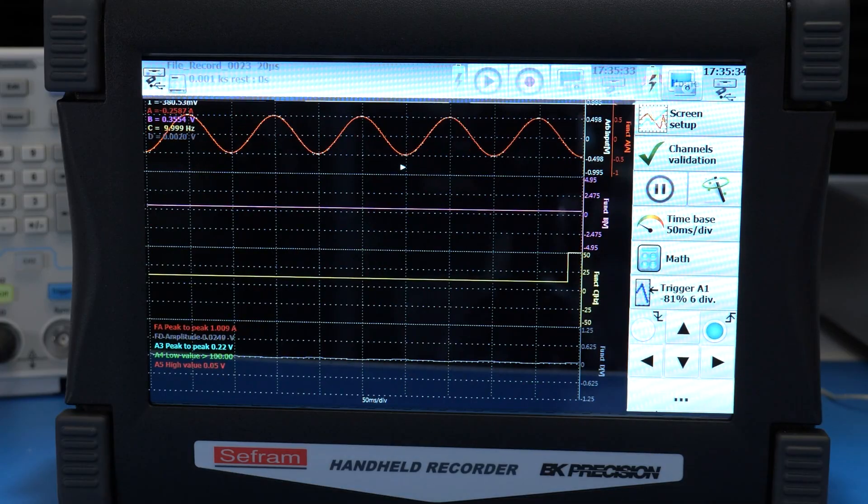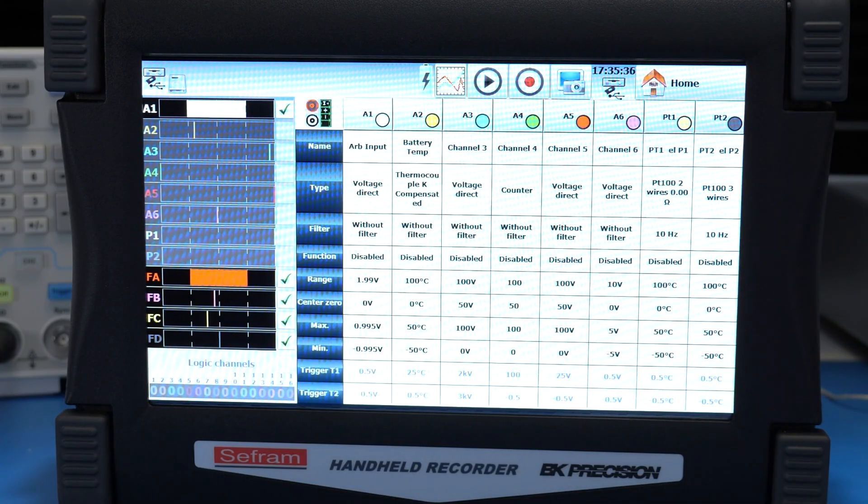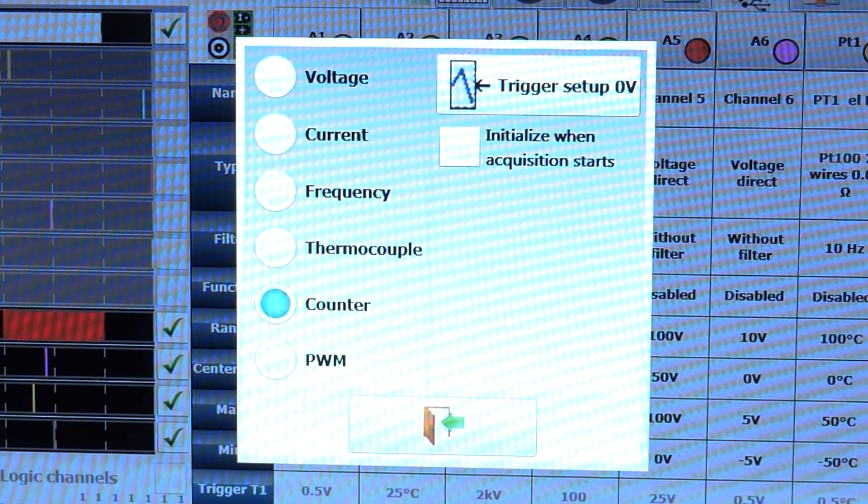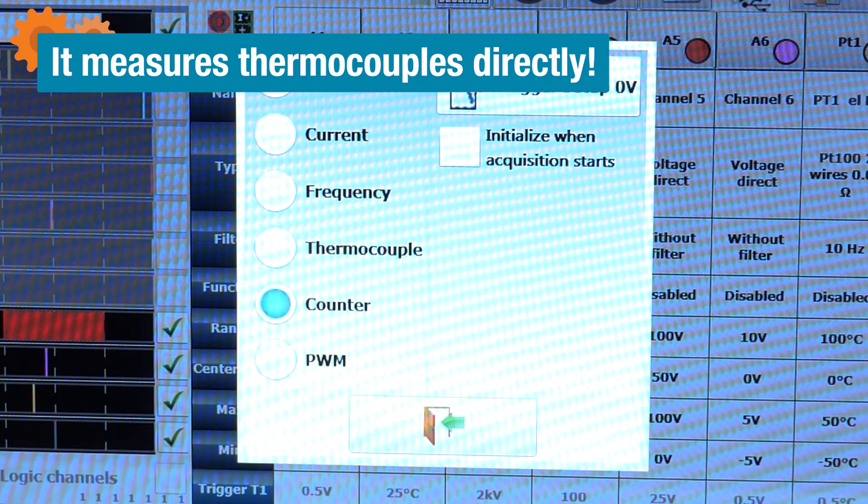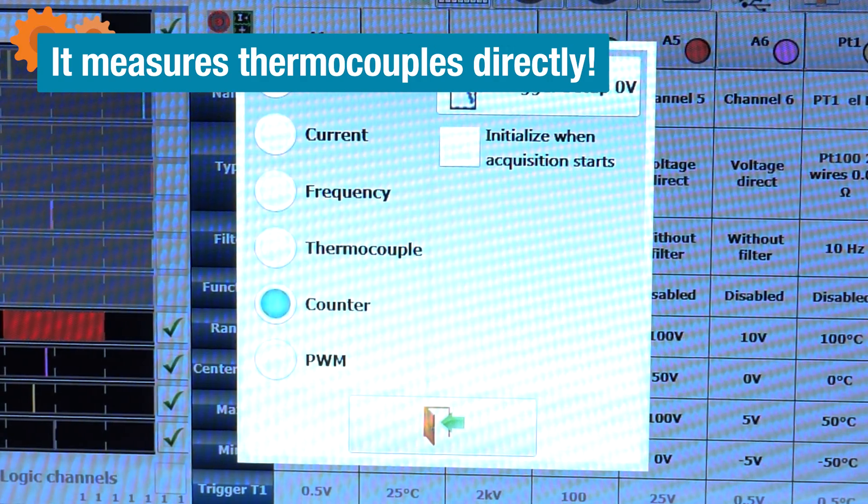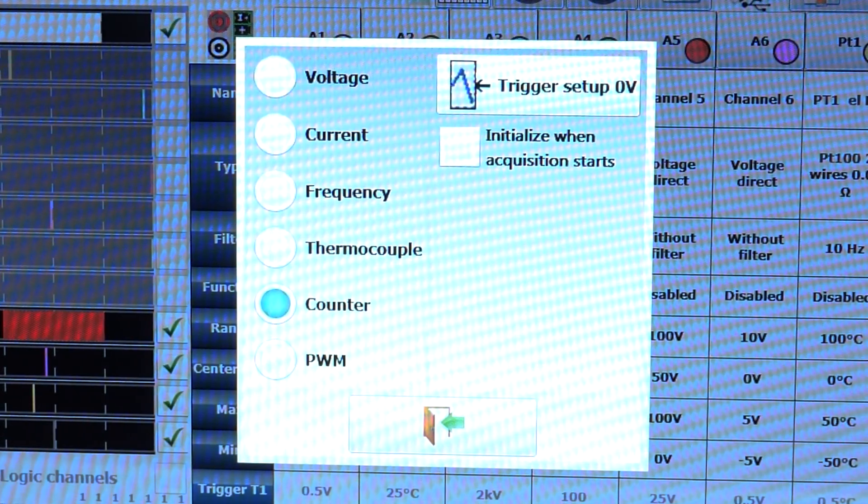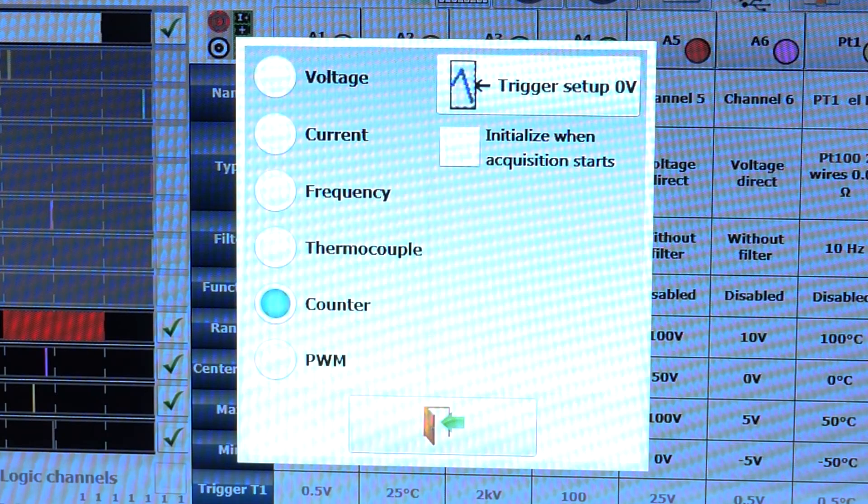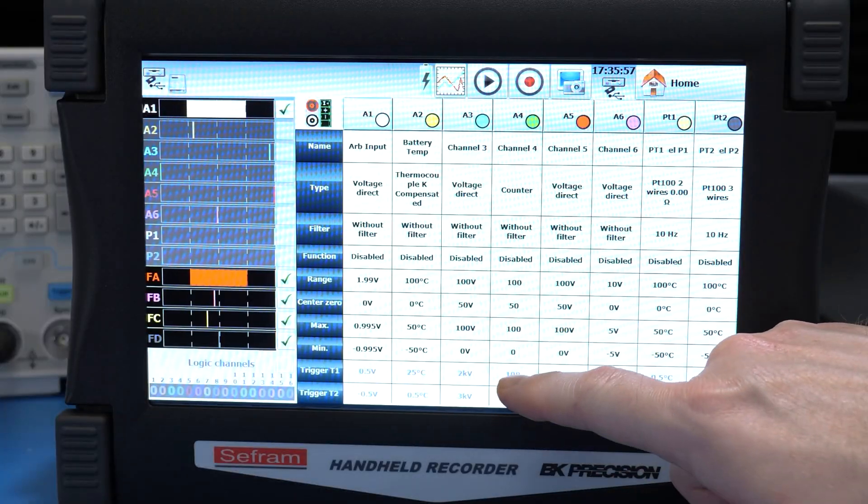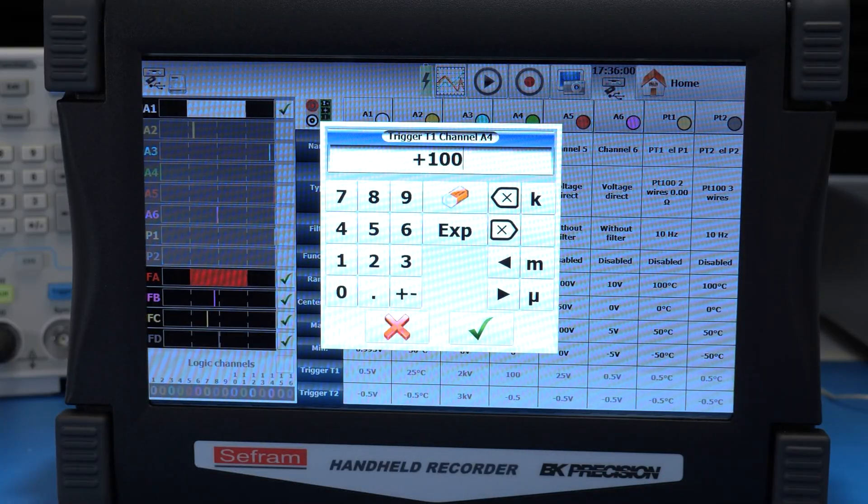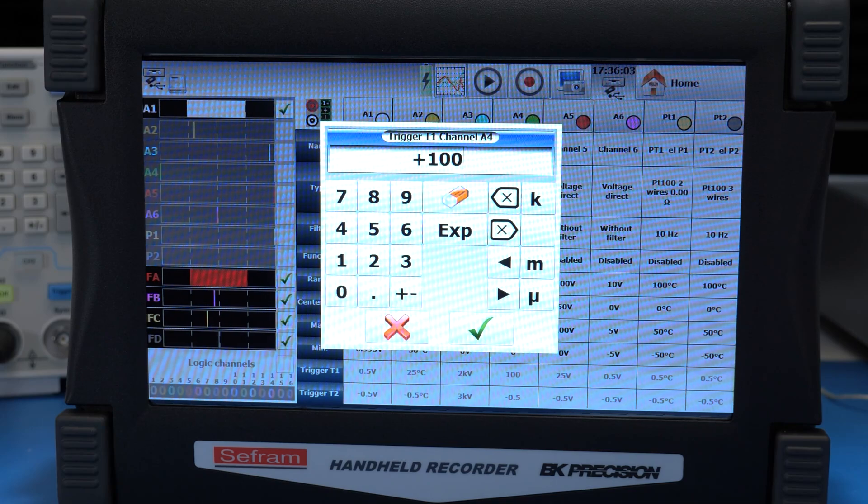Regarding the analog inputs, even though they only measure voltage, you can record other quantities. For example, they can also record frequency, or the duty cycle of a pulse-width modulated waveform, or they can count based on a threshold voltage. And any of these can create the start or stop trigger conditions I mentioned before when recording data.